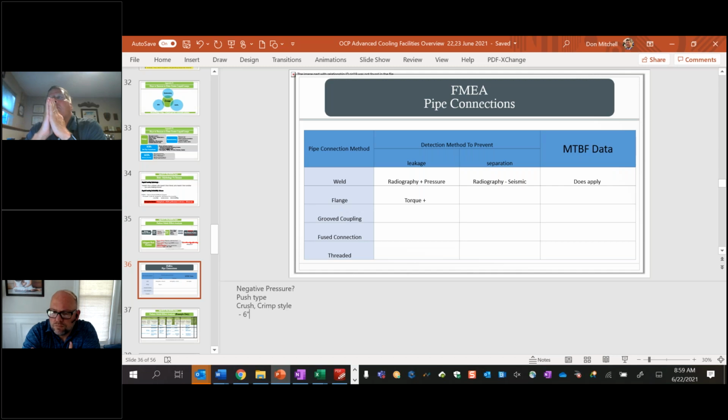And the way I ran PEX or welded systems like this was, you get, I can't remember the numbers now, I think up to 400 feet on one reel, maybe bigger. But when I ran through my critical spaces, I didn't have any welds in my critical space. I put them all out in the utility shaft, which was drained, kind of like a big elevator shaft, so that all my welded connections were out where they could be observed, and if they failed partially or catastrophically, I had solid paths over my critical equipment and it went into this waste zone otherwise. So essentially I had the longest run working around the critical equipment.